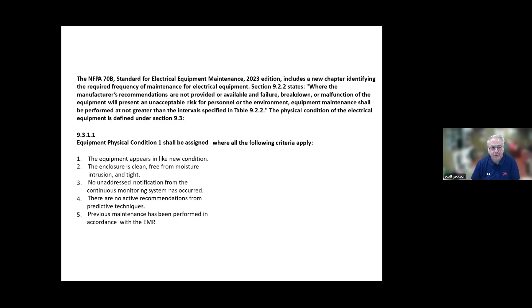Just so everyone knows - you build this nice new building and think, why do I have to maintenance it in the first year? Well, throughout the building construction process, all that drywall dust ends up in the switchgear. As an example, one customer was building a new building connected to their existing one, and in one of the rooms that was exposed were the gear and the UPS. An electrician opened the UPS door and it had an arc flash that put him through a wall. When they looked at the filter, it was caked with drywall dust. So just because it's new doesn't mean it doesn't need maintenance.